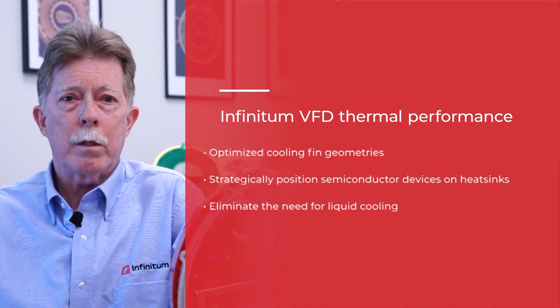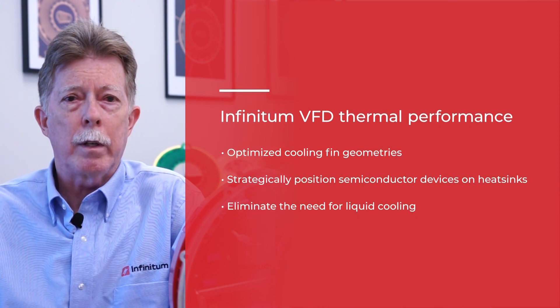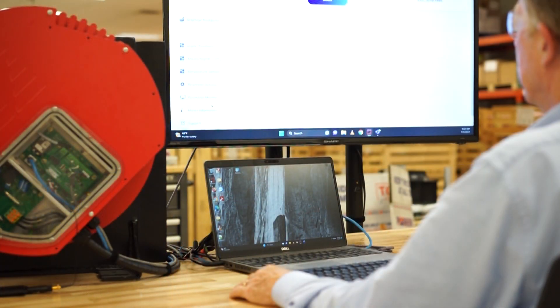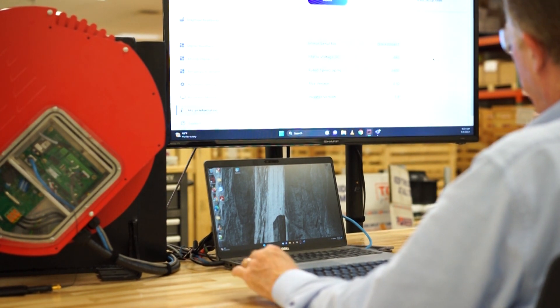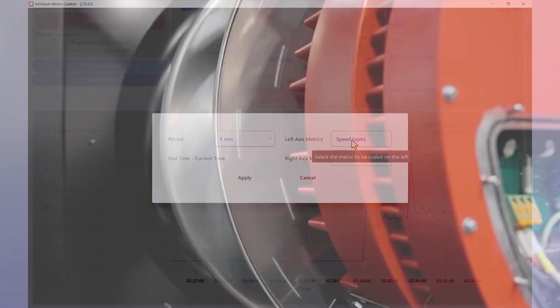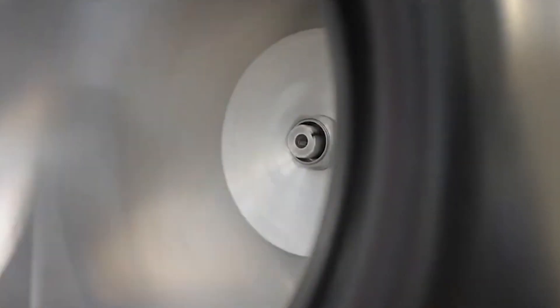For example, using real-time temperature monitoring, the VFD will issue an over-temperature warning and slow the motor down if heat buildup occurs. We designed our VFD and motor to meet the thermal performance of various load conditions. Through simulation, testing, and FMEA, we optimized the cooling fin geometries, strategically positioned the semiconductor power devices on heat sinks, and eliminated the need for liquid cooling. Infinitum's motor control software and hardware are designed for peak system performance. We optimized the control software to reduce losses, harmonics, and EMI. In addition, the physical proximity of the VFD to the motor reduces EMI and noise in the control signals.